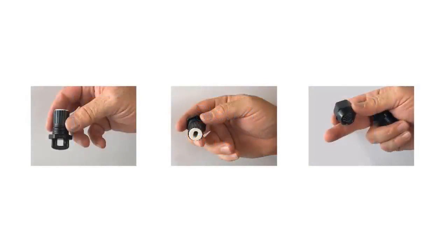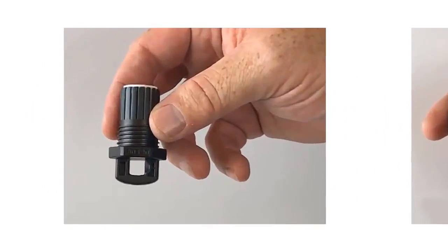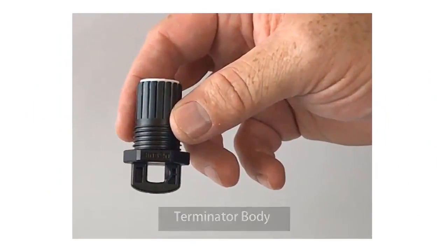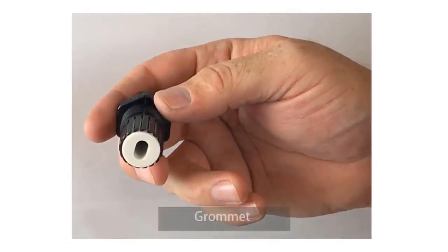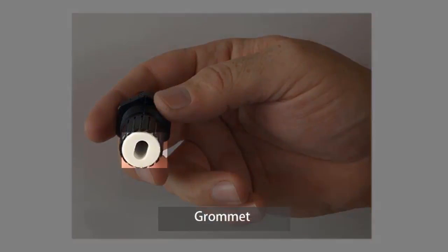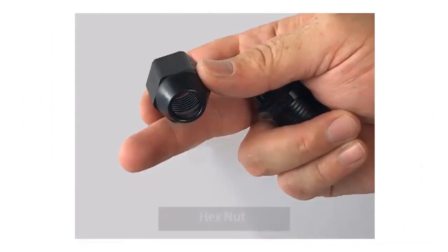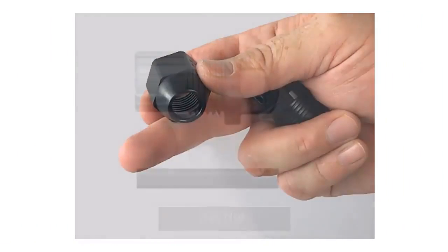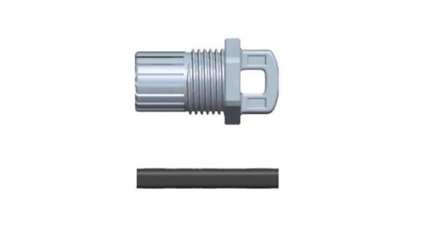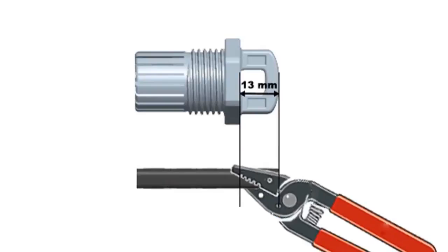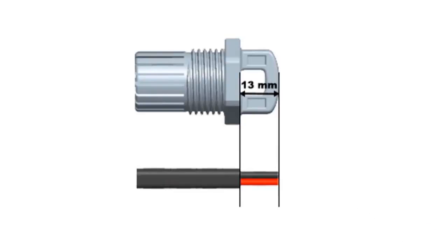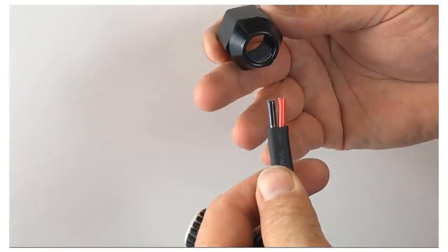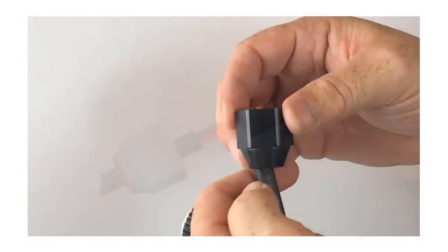Let's start by getting familiar with the terminator parts that you will need for assembly. This is the terminator body. This is the grommet that fits inside the terminator body. And this is the hex nut. Now let's assemble. Using the terminator loop to measure, remove 13 millimeters or 1/2 inch of the cable sheath from the conductors. Slide the hex nut onto the cable.